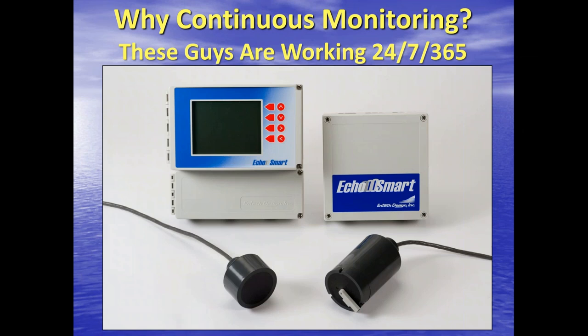That wiper that you see there is not intended to clear grease or heavy accumulations off the face of the sensor. It's there to wipe bubbles off the face of the sensor, because since these are underwater ultrasonic sensors, they have to be in the water to work. When they're out of the water, they're not getting a return signal. If there's enough bubbles on the face of the sensor, that can degrade or eliminate the signal.